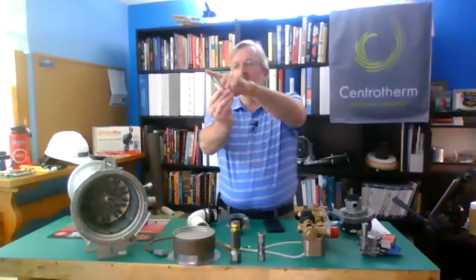So that's how that part of it works. It's how that air fuel mixture goes. Aside from that, in our combustion side, or our ignition side really, we have our igniter, which has a flame sensor built into it. So this is a Noble igniter, an igniter combination flame sensor. Our spark cable takes it back to our control board, which has the ignition module on it. We all spark there. Before I get too far ahead, something has to tell this thing to fire.